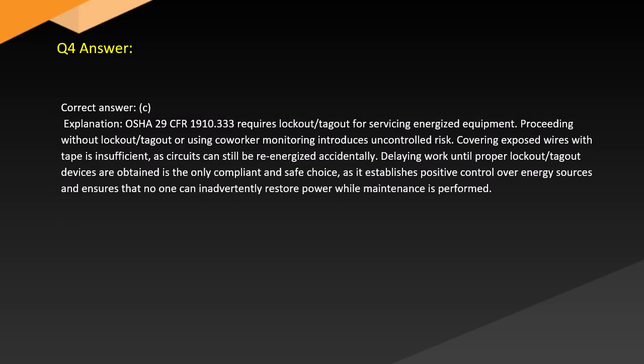Answer. Correct answer. C. Explanation. OSHA 29 CFR 1910.333 requires lockout/tagout for servicing energized equipment. Proceeding without lockout/tagout or using coworker monitoring introduces uncontrolled risk. Covering exposed wires with tape is insufficient, as circuits can still be re-energized accidentally. Delaying work until proper lockout/tagout devices are obtained is the only compliant and safe option, as it establishes positive control over energy sources and ensures that no one can inadvertently restore power while maintenance is performed.